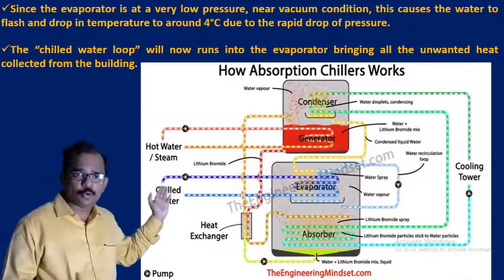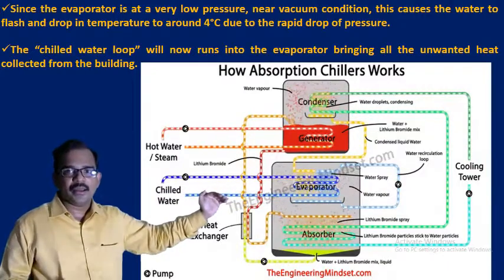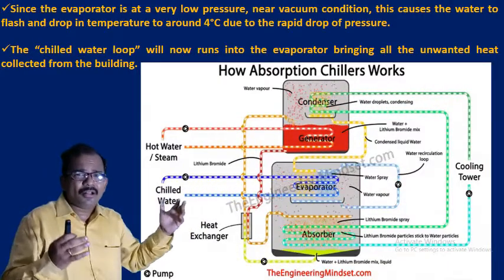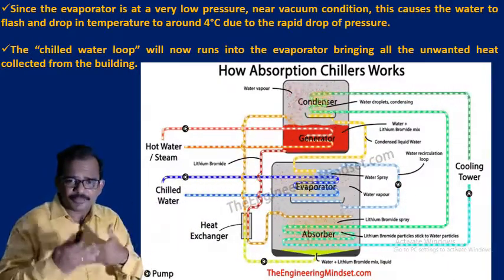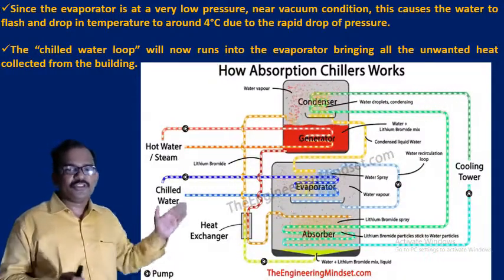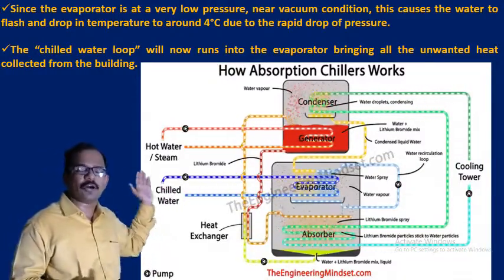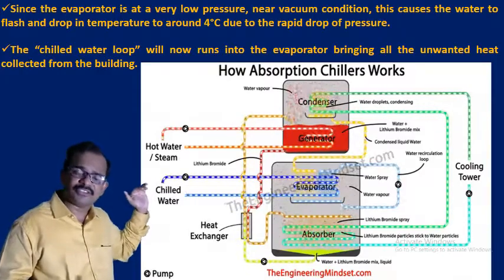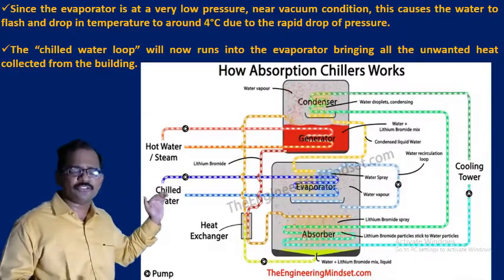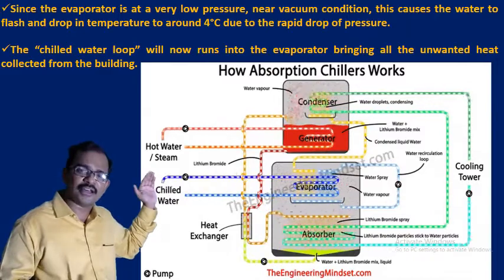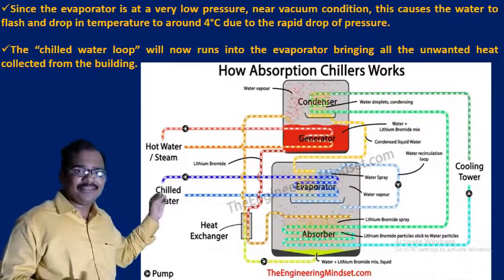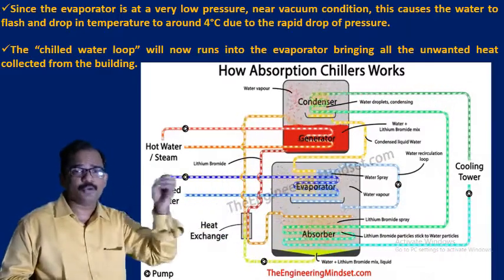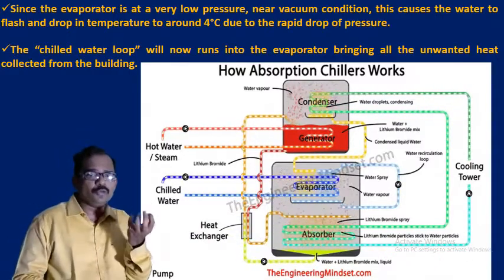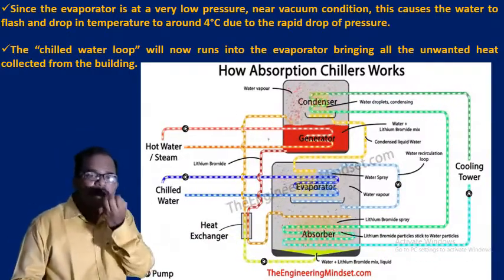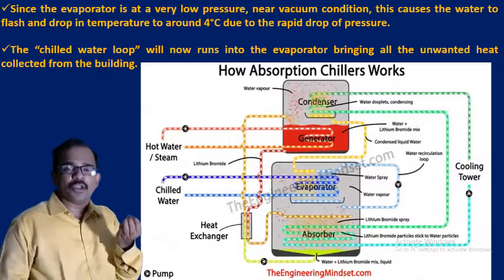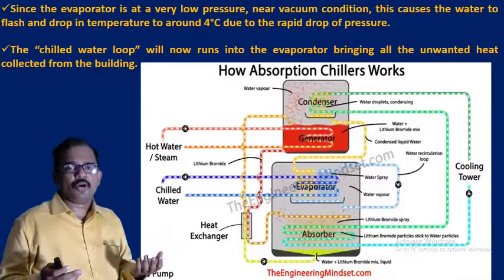Now this chilled water loop will run into the evaporator, bringing all the unwanted waste heat collected from the building. So this chilled water is the water which will collect all the unwanted heat in the building or facility from the refrigeration units or the fan coil units or from other ACs, and that will be sent into the evaporator. And this chilled water is a carrier for the waste heat which is coming from the industry or an organization.